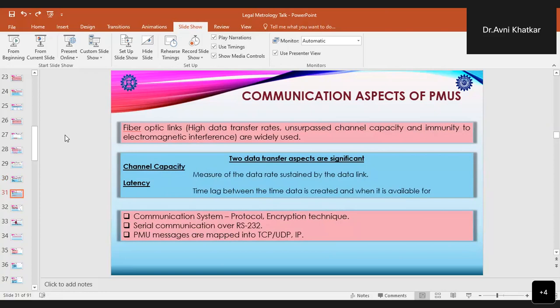Now, when we talk about the communication aspects of PMUs, the communication system for all the PMUs should be based on fiber optics. Even in the URTDSM scheme, it was recommended that the communication system for the PMUs be fiber optic, because with fiber optics we have higher data transfer rates, unsurpassed channel capacity, and immunity to any type of electromagnetic interference. Hence, fiber optic links are widely used.